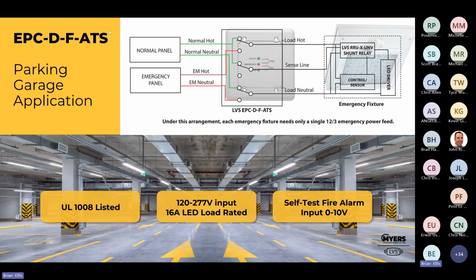So you can utilize the ATS transfer switch, put it in the electrical room with the normal power and the emergency power. This doesn't matter if it comes from a generator or an inverter, but think about if you draw this line right here, everything to the left is in the electrical room. And then these fixtures are all throughout the driveway, the drive area of the parking garage. So now we just run 3 conductors, which are going to be deemed all emergency, even though they're fed from utility and emergency, because everything downstream of a UL 1008 transfer switch is emergency, even though it's fed from utility and emergency.